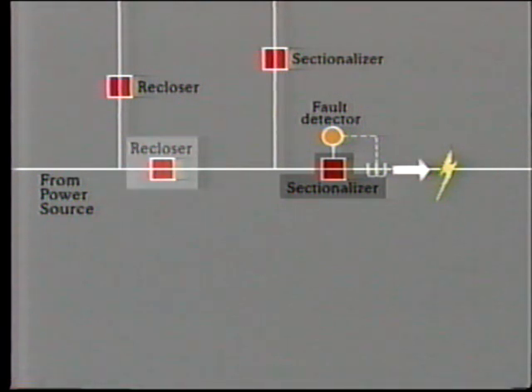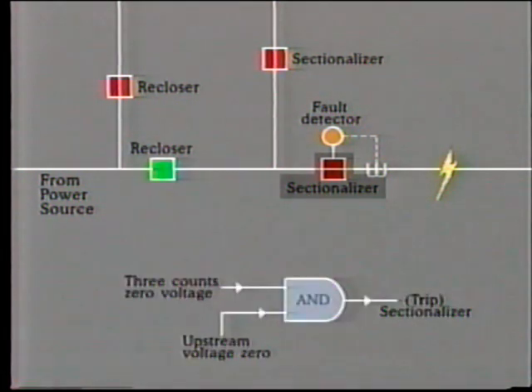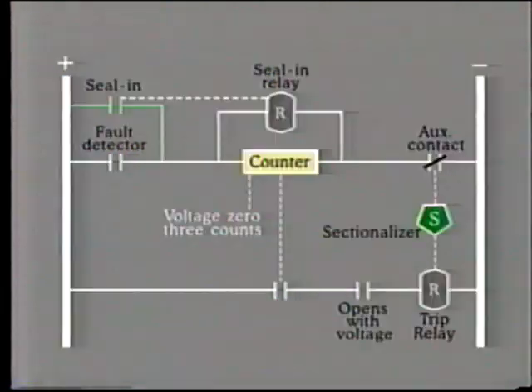First, we have the initial trip, then the first reclose, followed by a trip, and the second reclose, followed by a trip. So that is 3 counts of zero voltage. This is one condition for energizing the sectionalizer trip. A second condition is that voltage on the line is actually zero at the time. So this is an AND requirement. The circuit diagram would probably look like this.